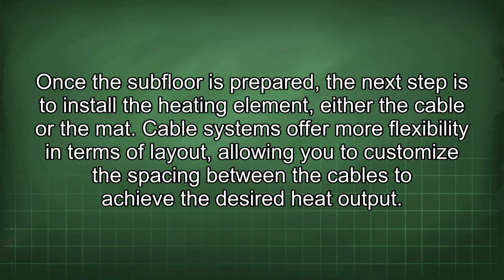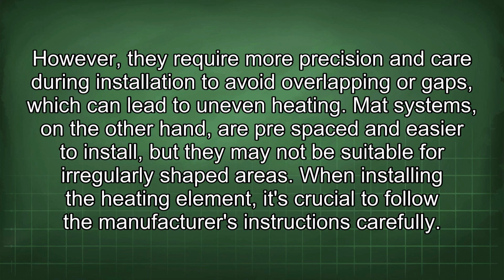Cable systems offer more flexibility in terms of layout, allowing you to customize the spacing between the cables to achieve the desired heat output. However, they require more precision and care during installation to avoid overlapping or gaps, which can lead to uneven heating. Mat systems, on the other hand, are pre-spaced and easier to install, but they may not be suitable for irregularly shaped areas.